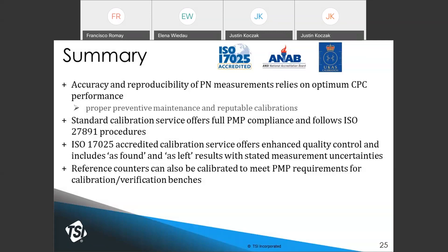If you order the ISO 17025 accredited calibration, which provides a higher level of quality control, it includes as-found and as-left measurements and stated measurement uncertainties that also account for external uncertainties. Reference counter calibrations are fully traceable to NPL but are not ISO 17025 accredited.